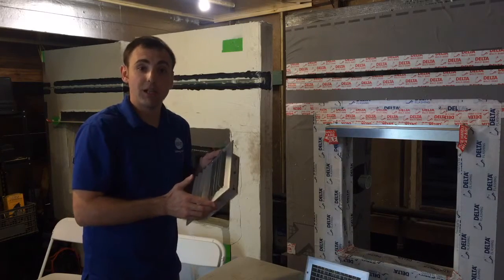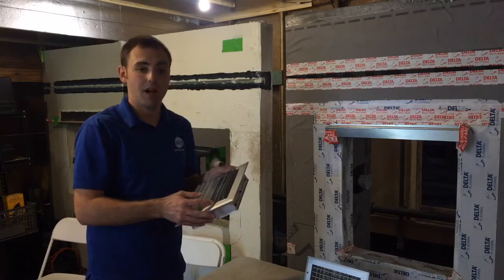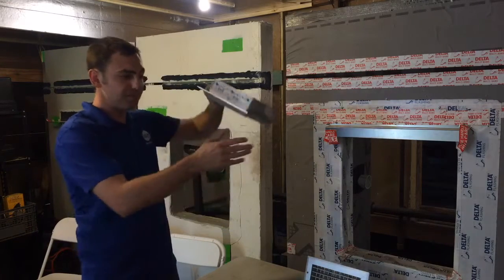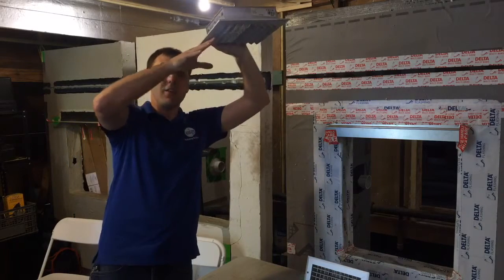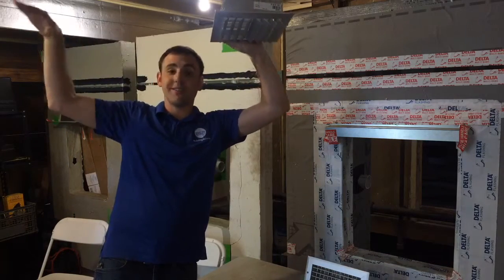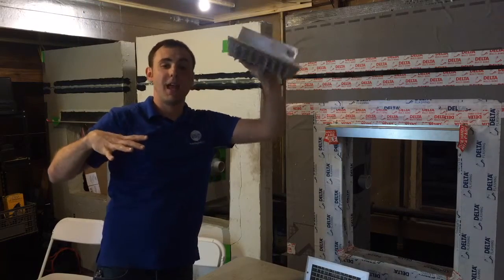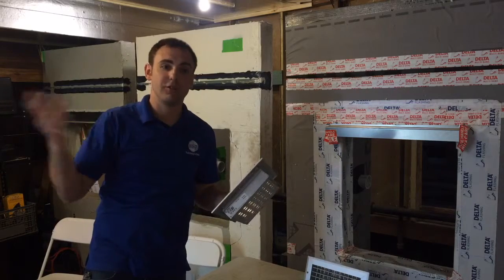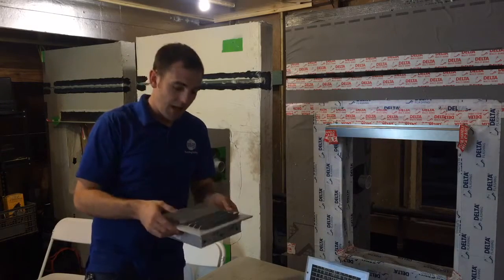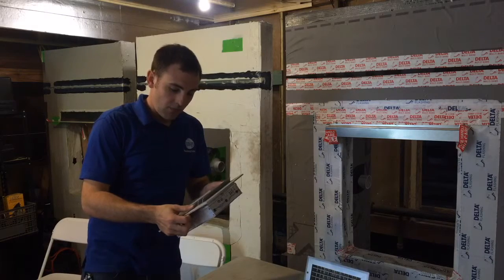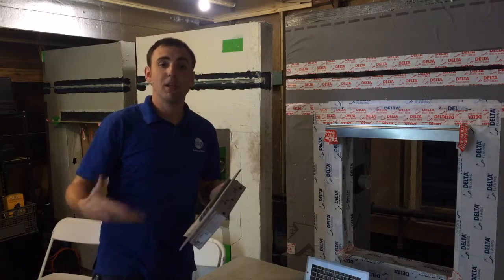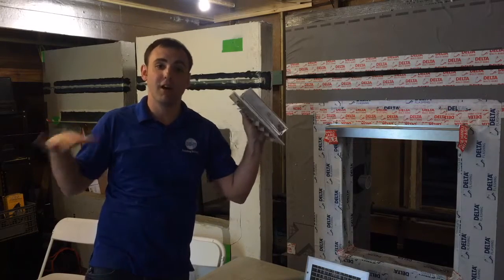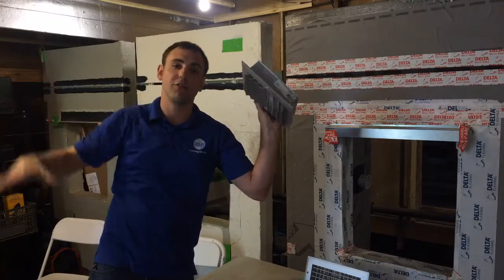The most control you can have is with a diffuser, and this one in particular is a curved vane diffuser. These curved vanes allow you to mount this on the ceiling, and the air comes out and sort of circles along the ceiling and then falls down. And the idea there is that you're cooling the room without blowing a bunch of uncomfortable air on someone. And in cooling climate zones like in Austin, Texas, where we are right now, this is the best way to deliver air into the room, because the cold air is then going to fall down.